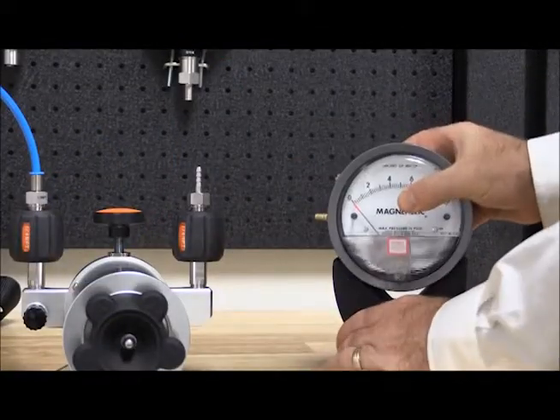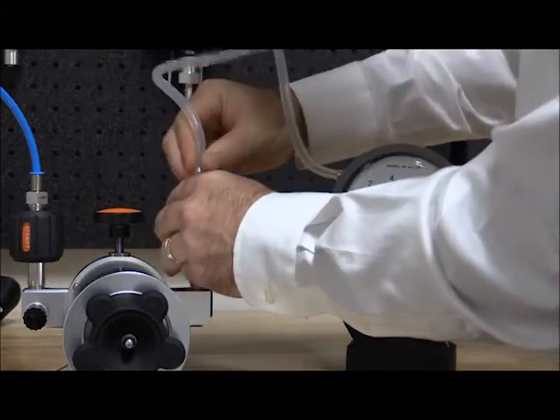It is important that the DUT is in the proper orientation based on its application use. This gauge was calibrated and used in a vertical position, so we will calibrate it in the same orientation.